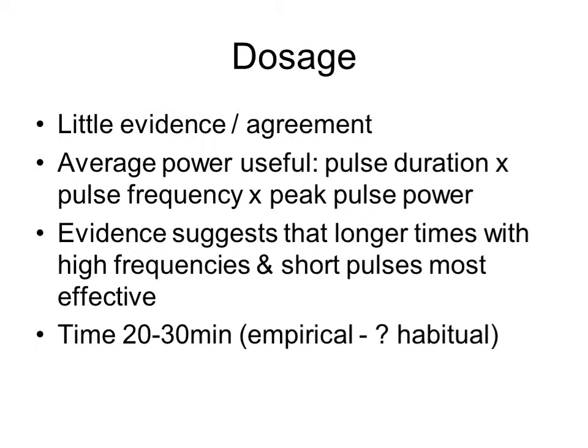In terms of dosage, there is little agreement or evidence in the literature. Having some idea of the average power seems to be useful, and this is a direct function of the duration of each pulse, normally fixed on most machines. The frequency of pulses and the peak pulse power or intensity are both normally adjustable. The evidence does seem to suggest that treatment for longer time periods using higher frequencies and short pulses might be more effective. The normal treatment time recommended is between 20 to 30 minutes, but there seems to be no clear rationale for this except that it fits well with the time that patients often have for a treatment session.